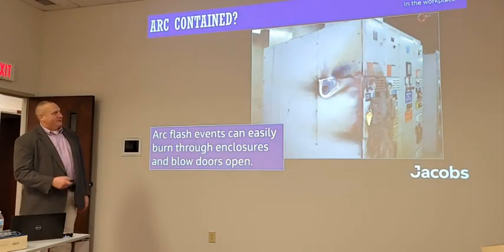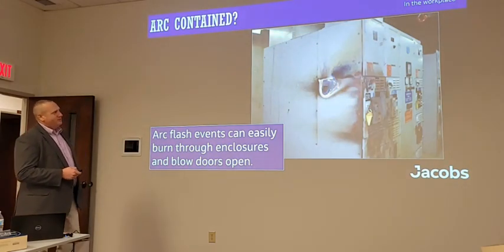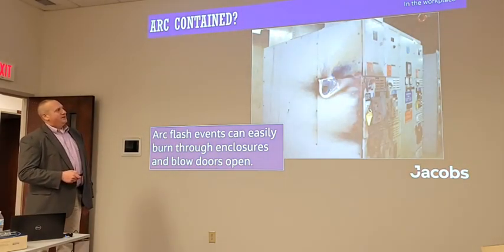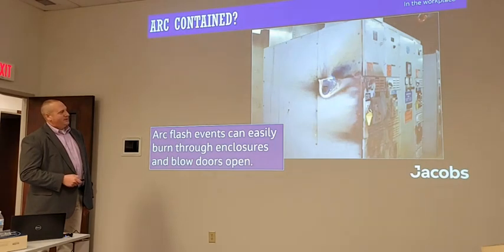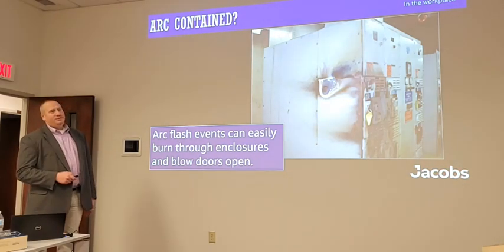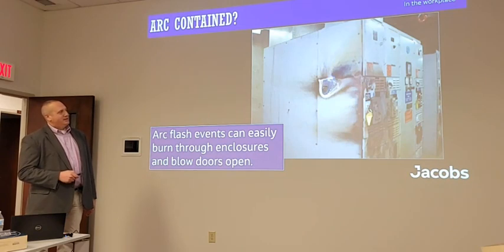And I like to show this picture because if you're familiar with this era of equipment, these metal or steel panels, when you unbolt them, they are a bear. I mean, it's huge, thick steel. And this, granted, this had to have been a long duration, bad protection situation, but the arc actually burned all the way through a hole right through the side of that. So that was significant arcing to come through there.